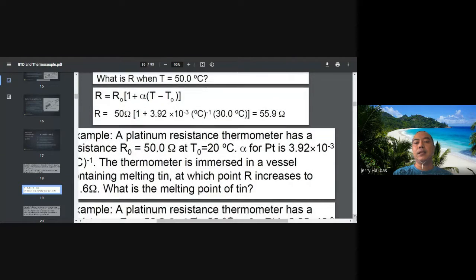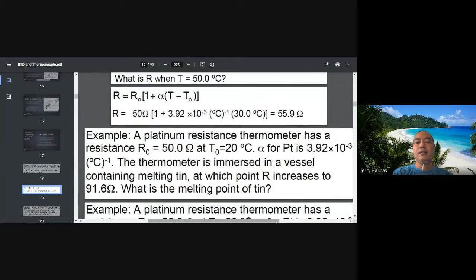Okay? Then another question, no? Given your initial resistance, 50 ohms, again, at 20 degrees ambient temperature, same alpha. However, the RTD sensor is immersed, or you could say a thermometer is immersed in a vessel containing melting tin. So take note, tin is a metal that was melted. The question now is, what is the final temperature, no, or the melting point of the tin, as the resistance of your thermometer increases to 91.6 ohms.